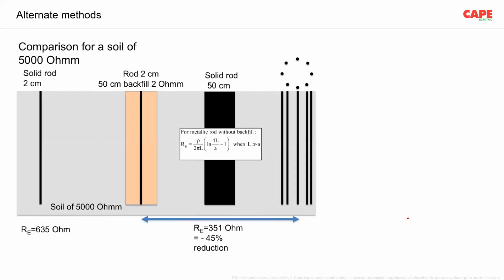Now, the alternate method: you can see here on the table, on the left side, you have a normal rod. The soil resistivity is 5000 ohm meter, a normal 20 mm rod, you get a resistance of approximately 635 ohm. Now, all around the same rod, a 50 centimeter backfill compound is used. 50 centimeter, 500 mm, almost half meter of backfill compound is used, and the backfill compound has 2 ohm meter.